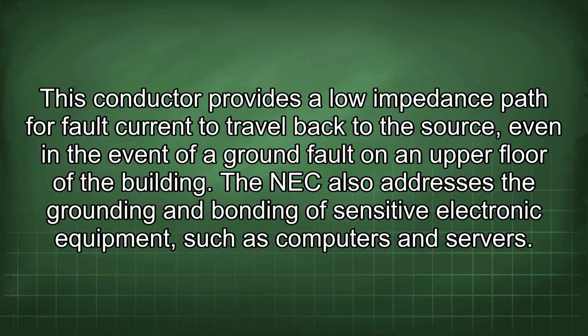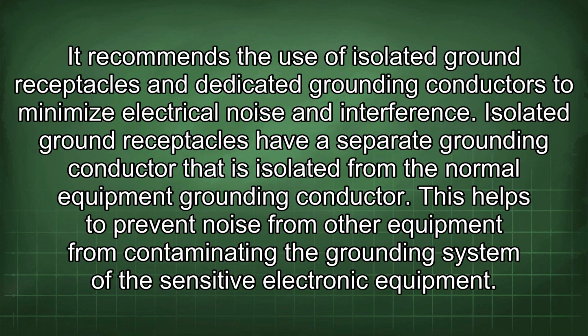The NEC also addresses the grounding and bonding of sensitive electronic equipment, such as computers and servers. It recommends the use of isolated ground receptacles and dedicated grounding conductors to minimize electrical noise and interference. Isolated ground receptacles have a separate grounding conductor that is isolated from the normal equipment grounding conductor. This helps to prevent noise from other equipment from contaminating the grounding system of the sensitive electronic equipment.